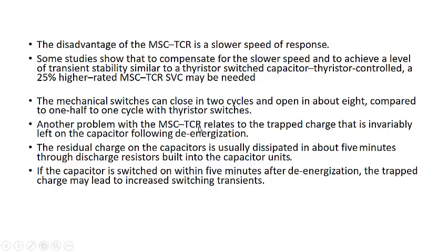Another problem with the MSC TCR relates to the trapped charge that is invariably left on the capacitor following de-energization. When we open the mechanical switch, it results in trapped charge left on the capacitor. So that is actually a danger. The residual charge on the capacitor is usually dissipated in about 5 minutes through discharge resistors built into the capacitor units. But this is again a long time to discharge, because sometimes you may require the capacitor before this 5 minutes. So in that case, it is very difficult. So this is also a disadvantage.